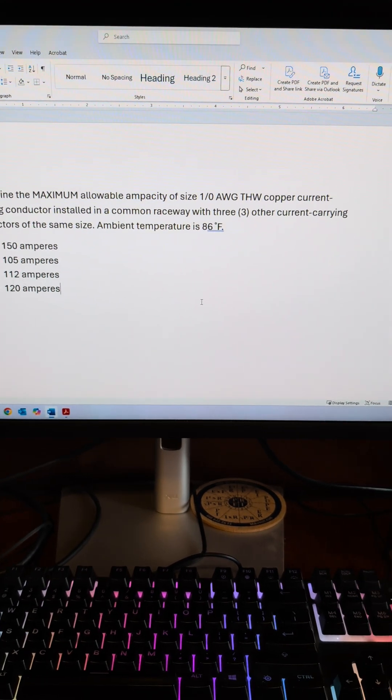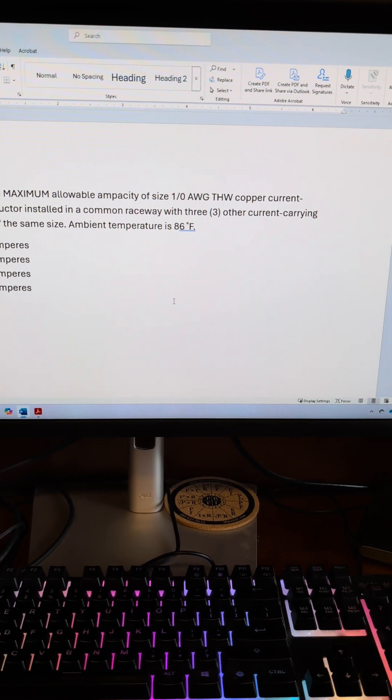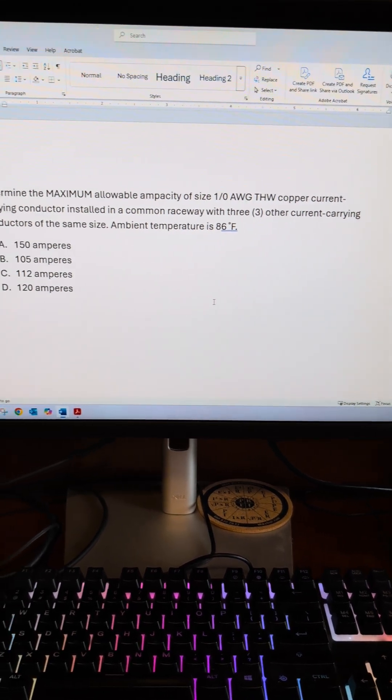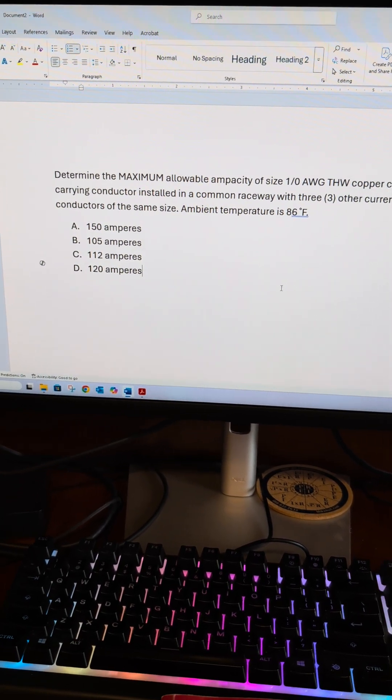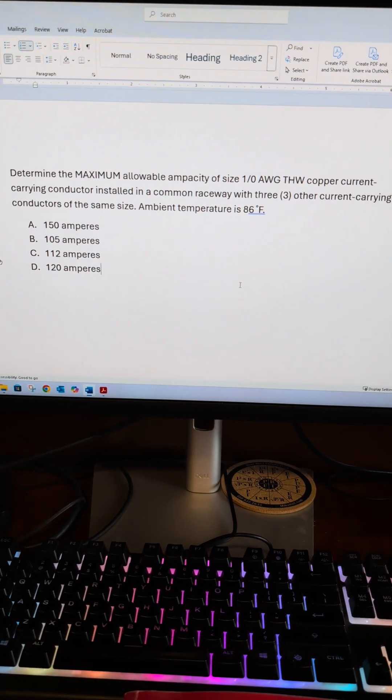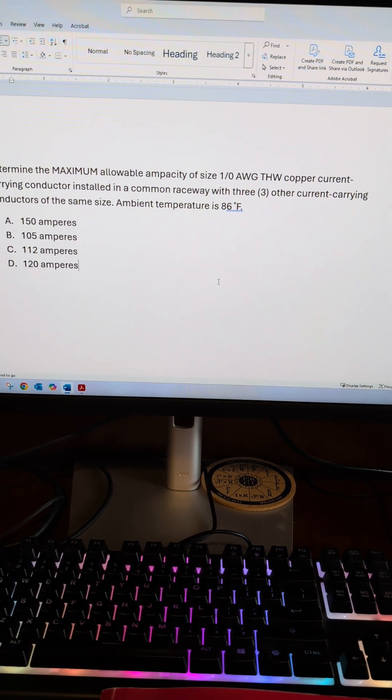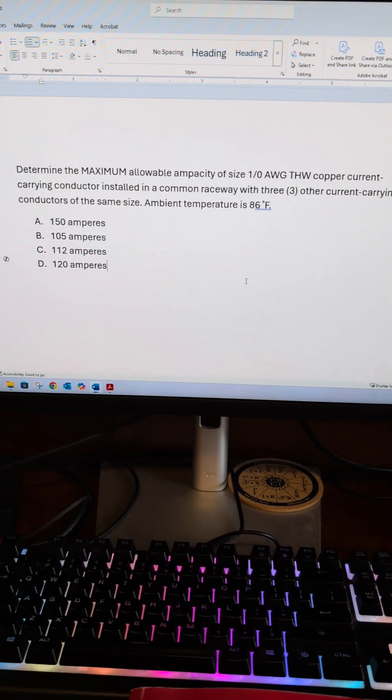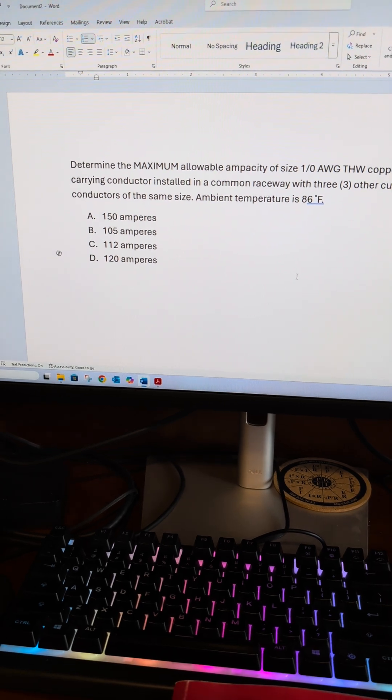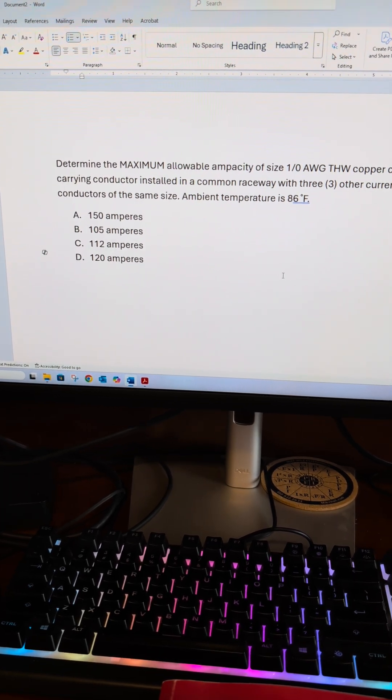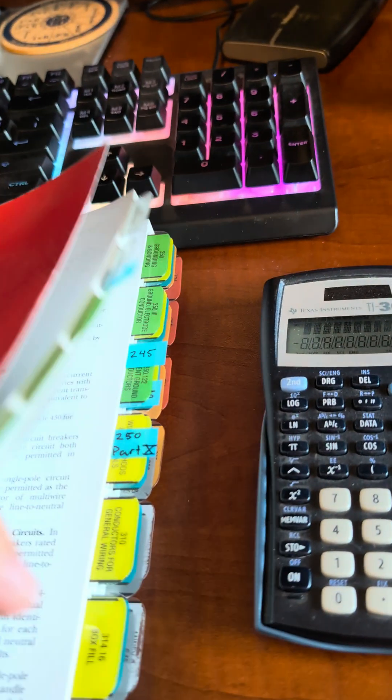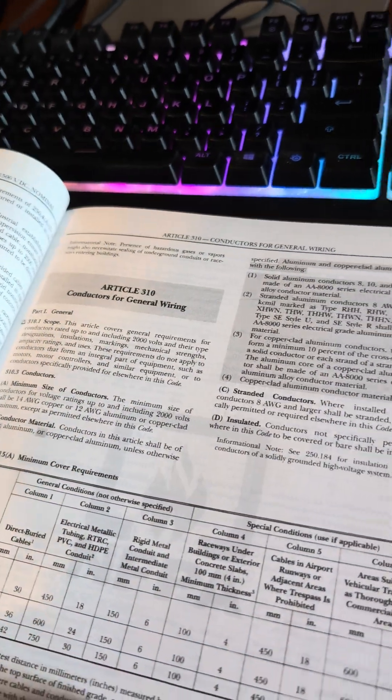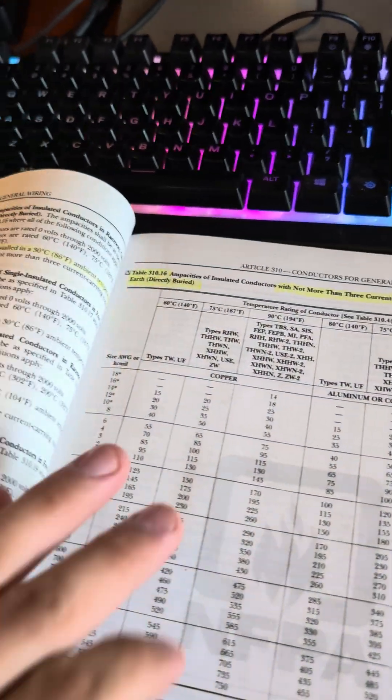Determine the maximum allowable ampacity of 1/0 AWG THW copper current carrying conductors installed in a raceway with three other current carrying conductors of the same size. The ambient temperature is 86 degrees Fahrenheit. We are looking for ampacity, and you should know this is Article 310, Table 310.16.